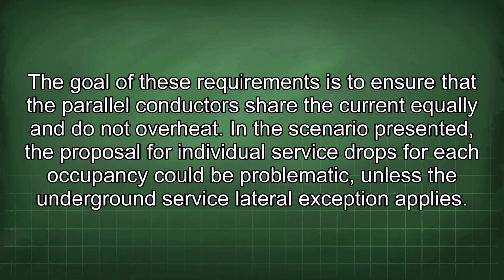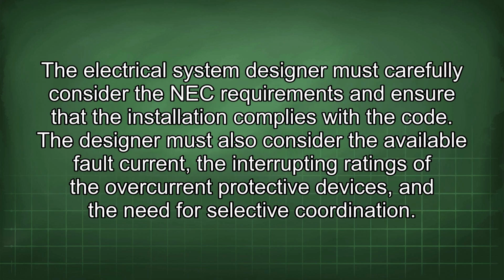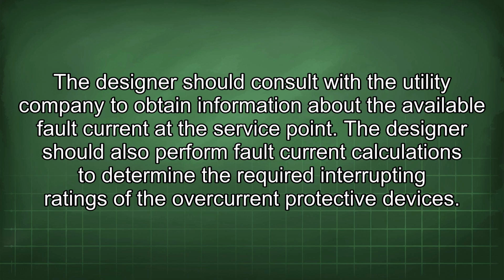In the scenario presented, the proposal for individual service drops for each occupancy could be problematic unless the underground service lateral exception applies. The electrical system designer must carefully consider the NEC requirements and ensure that the installation complies with the code. The designer must also consider the available fault current, the interrupting ratings of the overcurrent protective devices, and the need for selective coordination. The designer should consult with the utility company to obtain information about the available fault current at the service point.